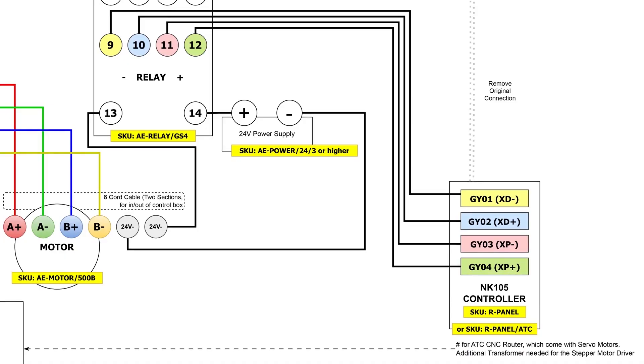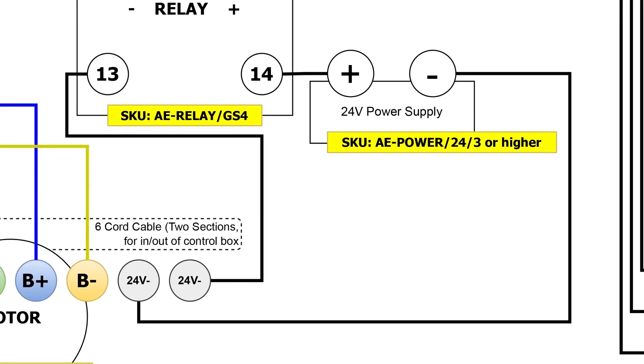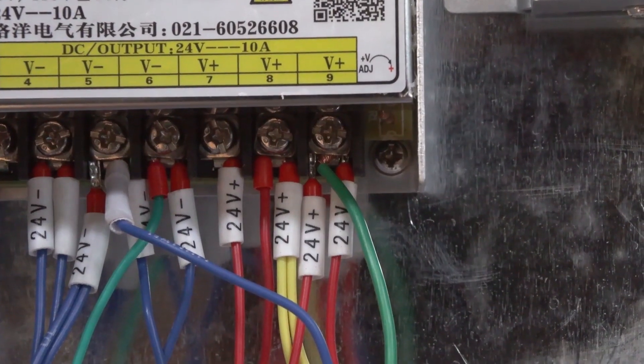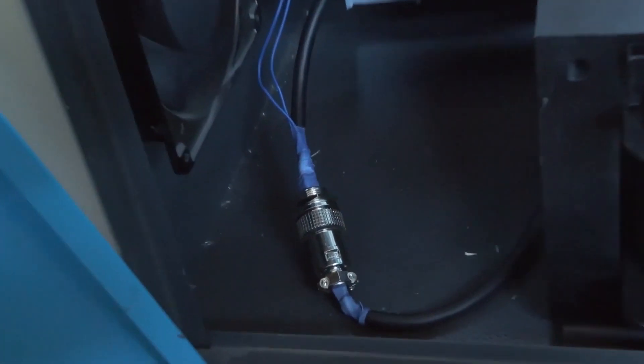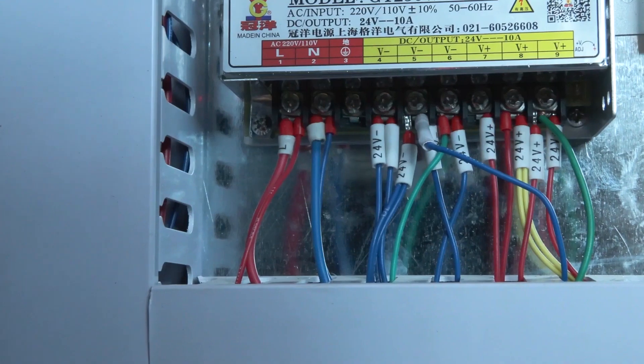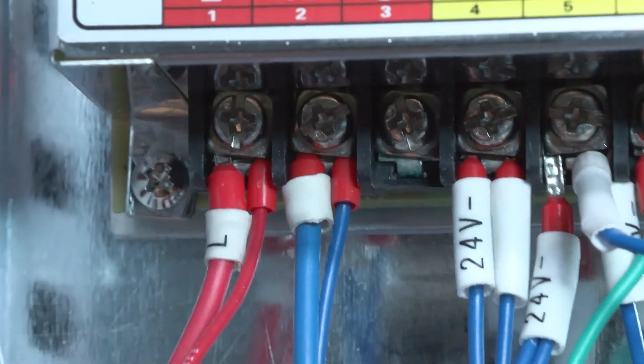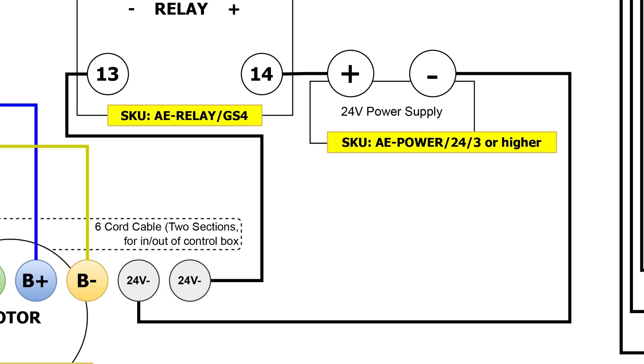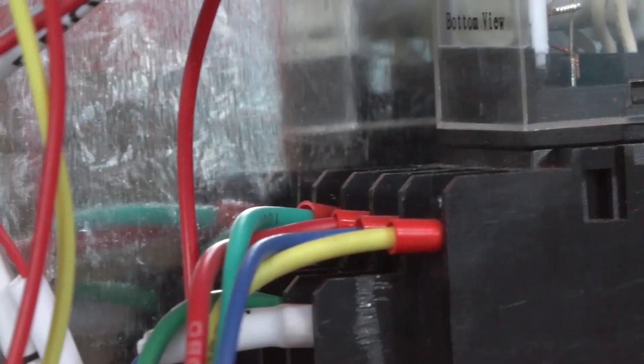Now what is left is the switching cable. Terminal 14 on the relay goes to a positive 24-volt power supply, the negative side of which is joined to one side of the cable marked 24-volt negative. The other side of the cable marked 24-volt negative goes to terminal 13 on the relay.